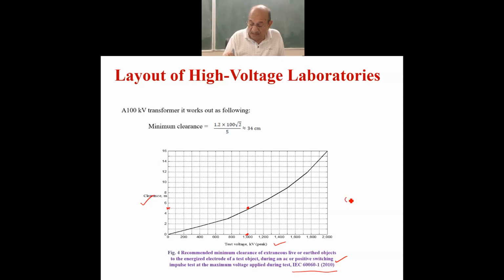You can say the requirement is 0.5 centimeter per kV peak. Sorry, I've written it wrong. I'm saying centimeter, writing kV peak. So this is a thumb rule. For all types of voltages, you keep a clearance of the order of 0.5 centimeter per kV peak. This is recommended by the IEC.